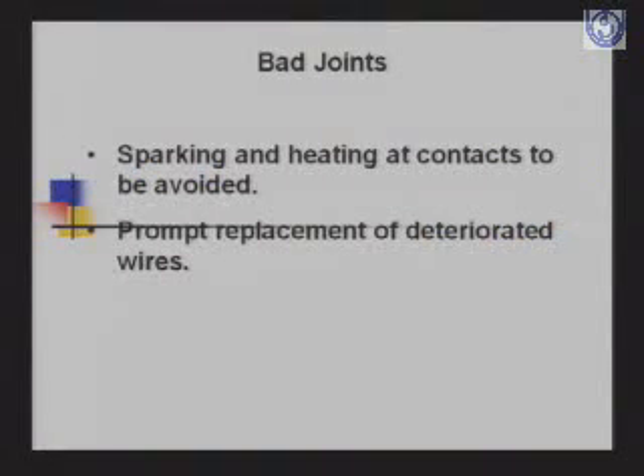Towards loss we only consider I²R loss and loss in transformers. But actual studies indicate that losses can be as high as 3 to 4% in joints. So these joints should be very carefully made. Sparking and heating at contacts should be avoided. You should have prompt replacement of deteriorated wires wherever sparking is occurring.